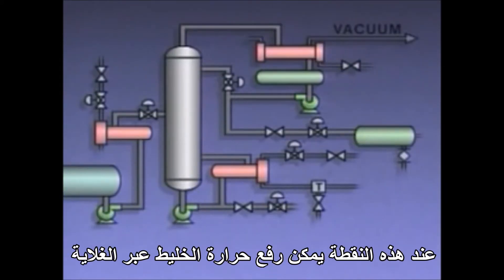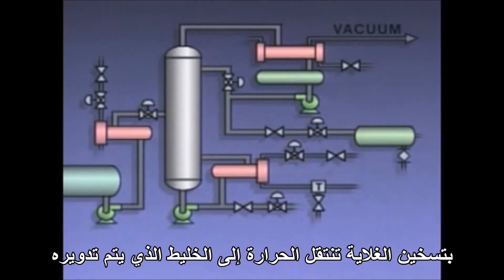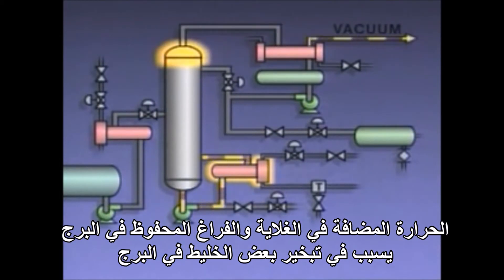At this point, heat can be applied to the mixture in the reboiler. To do this, a temperature controller is used to open a steam valve to the reboiler. As the reboiler warms up, it transfers heat to the circulating mixture. The heat added in the reboiler and the vacuum maintained in the column causes some of the mixture in the column to vaporize.